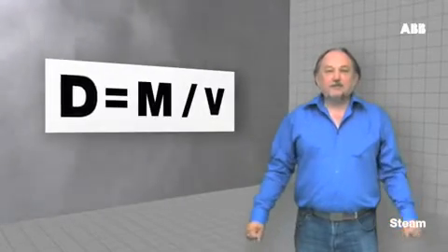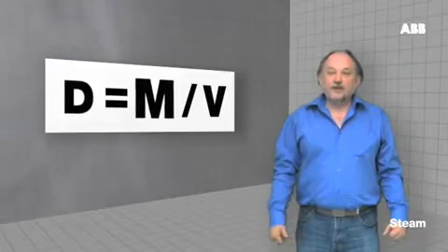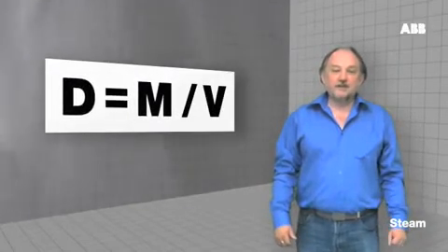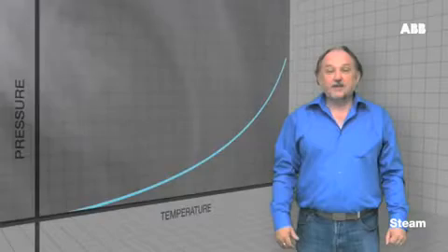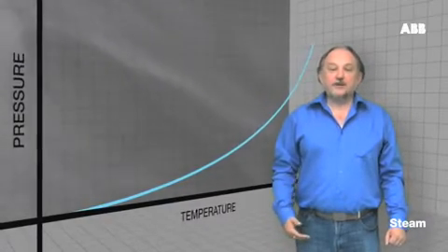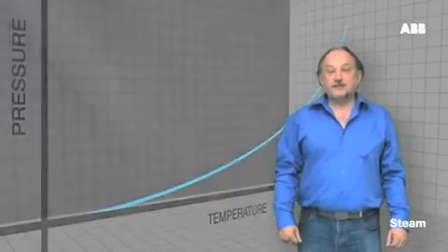The relationship of steam density, mass, and volume is very similar to gas. But for dry saturated steam, which is normally used in boiler steam plants and steam distribution networks, the density is directly proportional to a defined temperature and pressure curve. This reduces the number of variables that need to be considered.